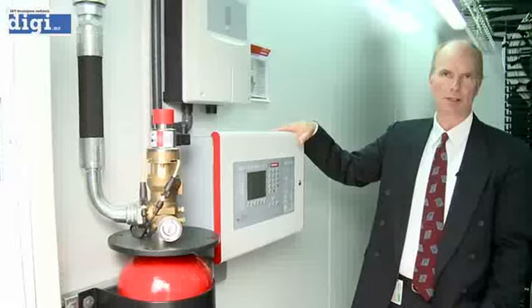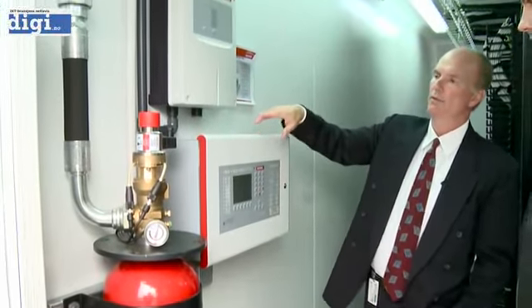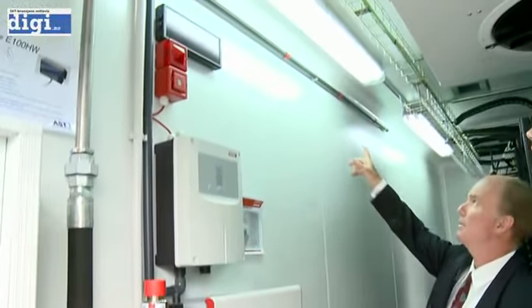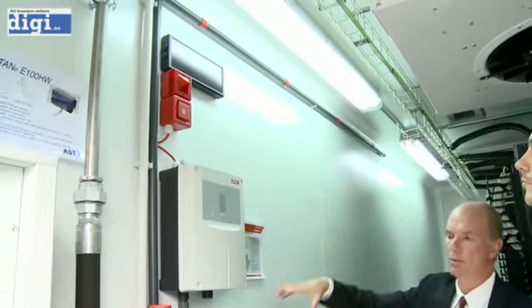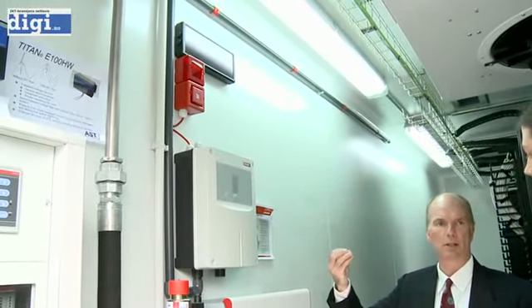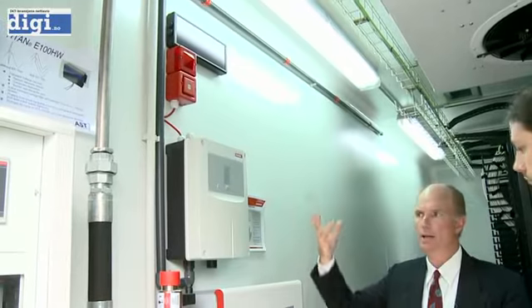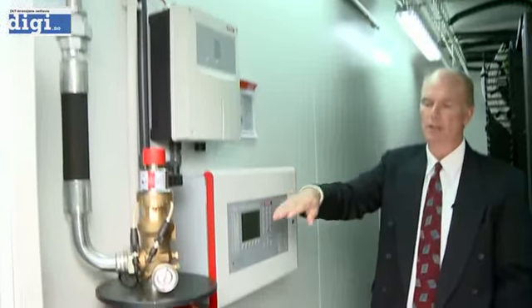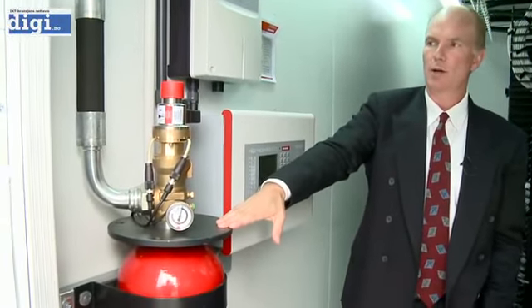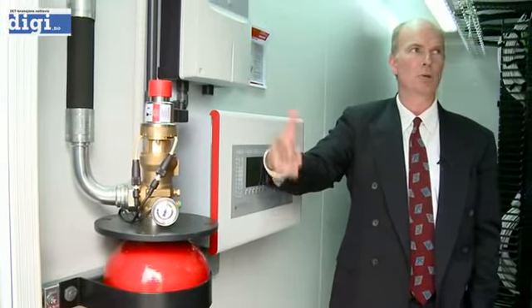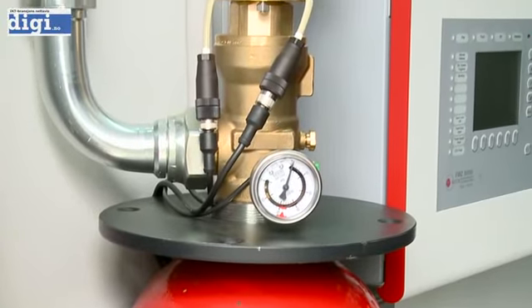This is the fire detection and suppression system. We have a VESDA system that takes air samples constantly, checking for any particulate that might signal a fire. If it senses a fire, we release a gas - in this case Novec gas, because it's safe for humans. We could also use other types of gas, like Inergen or FM200.